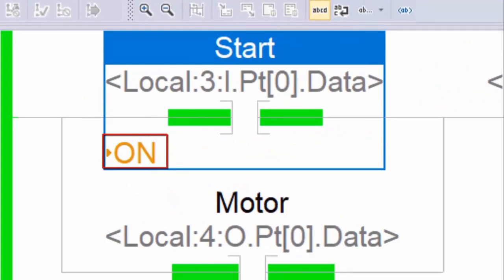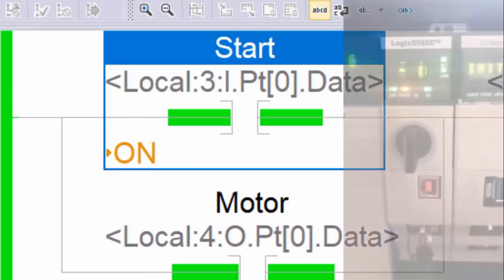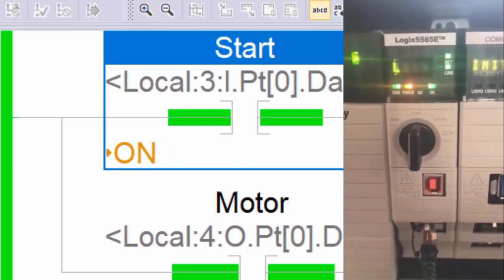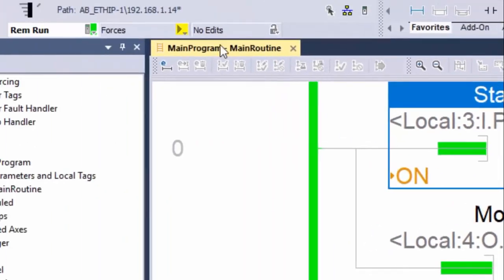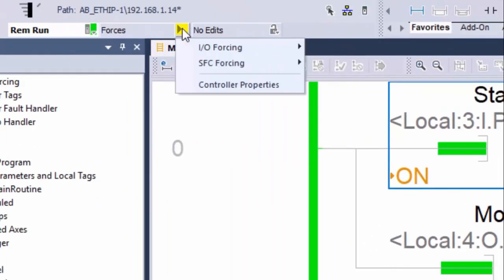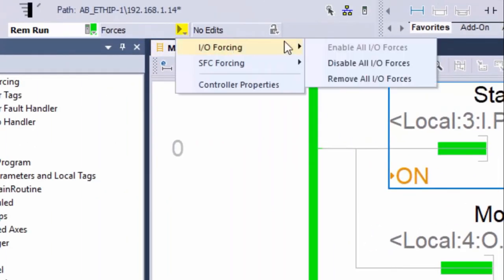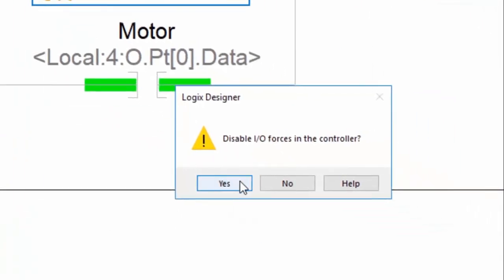The play sign next to the on label informs us the force is now active in the controller. The real value of the digital input 0, the start tag value, is now forced to 1. From the controller lights, we can also see that the forcing LED is now solid. To disable this force, go back to the force menu and click disable all IO forces. When the confirmation window is prompted, click yes.